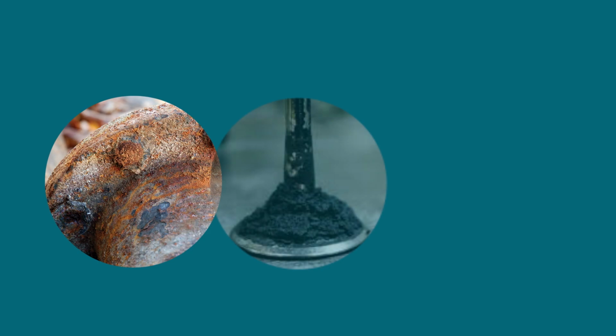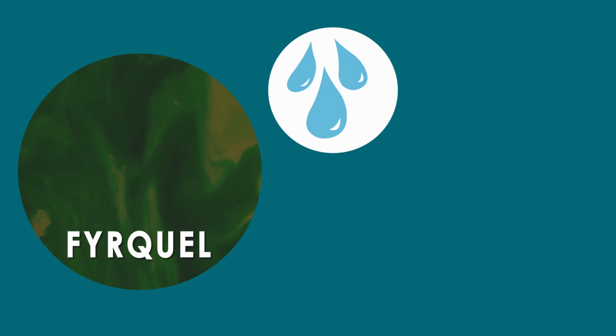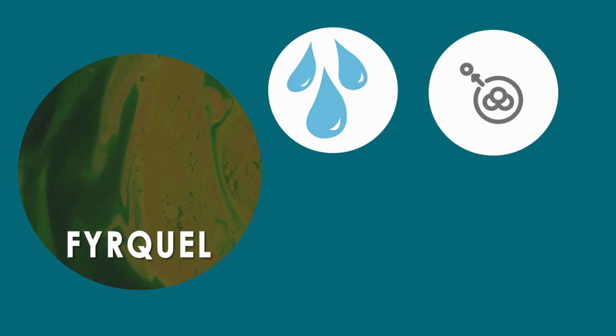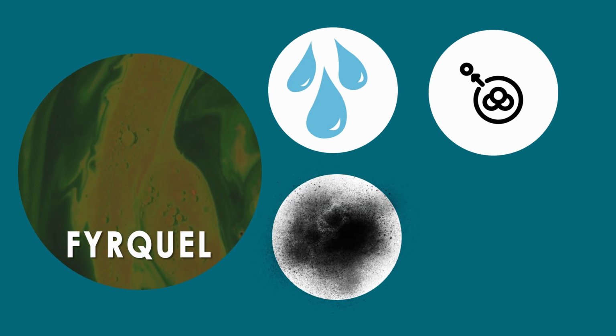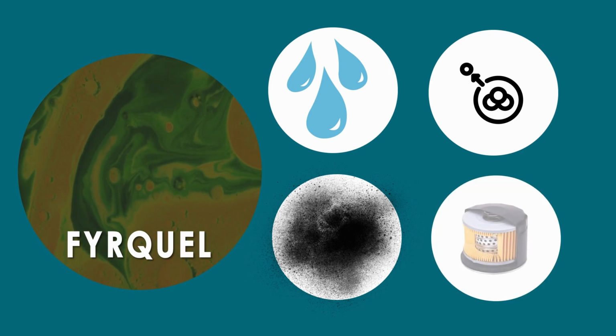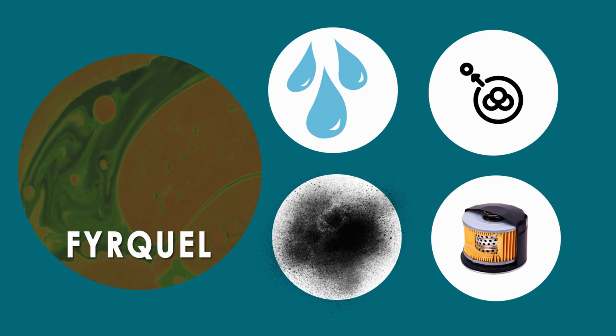The most common problems encountered by Fyrquel fire-resistant hydraulic fluid while in use include hydration, which triggers the decomposition of phosphoric acid esters with formation of alcohols and acids. Oxidation, which, along with a high temperature, contributes to decomposition of Fyrquel fluid. Contamination and decomposition products cause a decrease in resistivity, and a low resistivity fluid can give rise to corrosion of valves. Clogging of filters. When exposed to extreme temperatures, Fyrquel fluid develops dark particles, which cause silting of valves and accelerate clogging of fixed filters as time goes by.